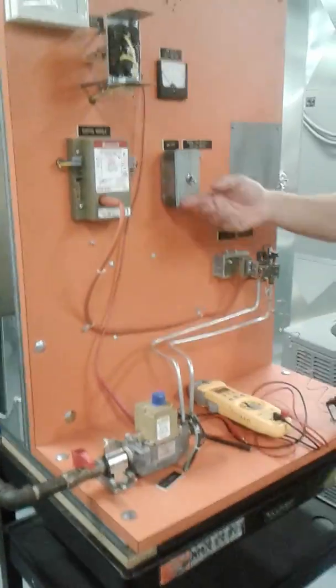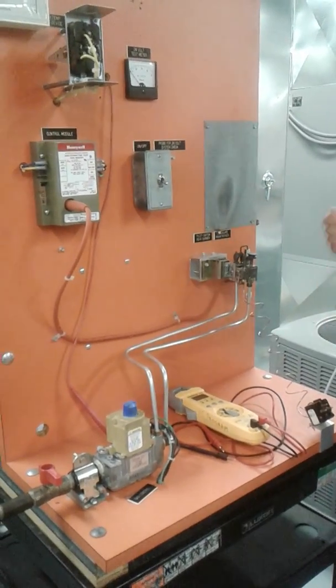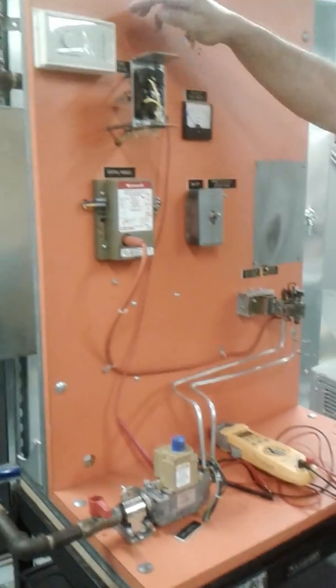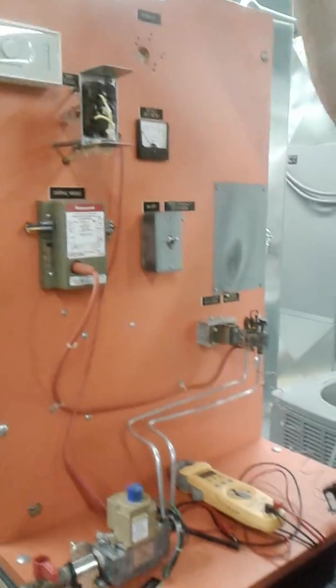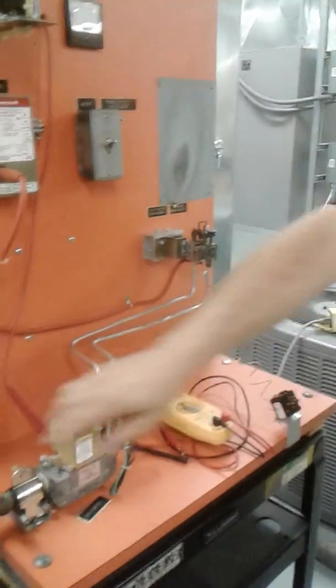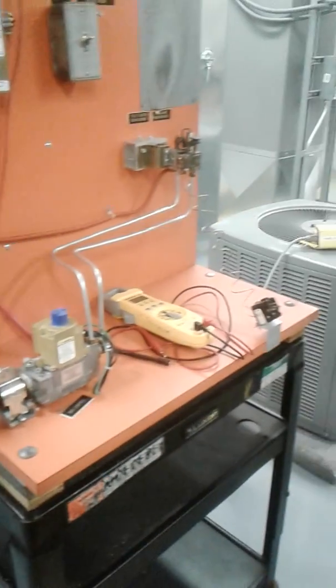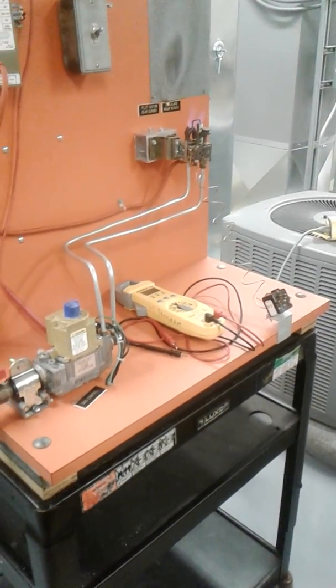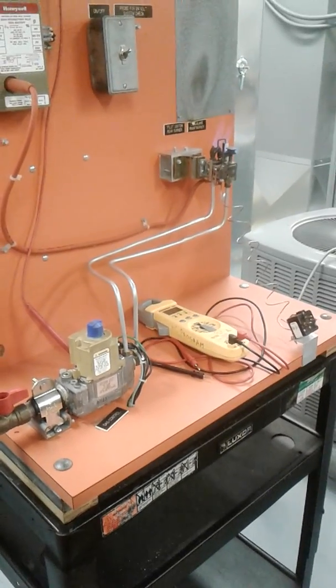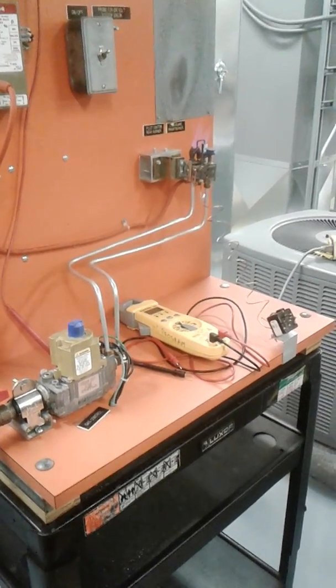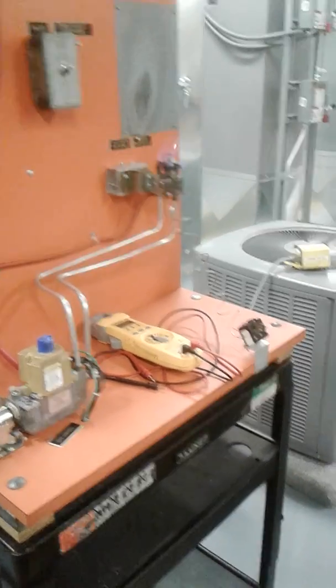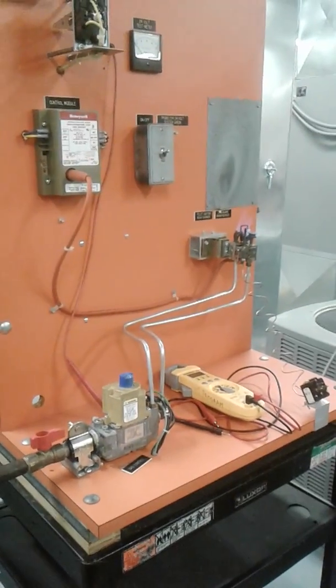In fault 3. Okay? Now, we already know how to turn this unit on. Make sure the gas is turned on. This is the power switch. This is actually the switch on the side of the furnace. Call for heat. The gas on. And the unit lights. Now it says here, turn on the gas shutoff valve, provide spark to the trainer. We did that. Set the system, or plug in the cord, so on and so forth.